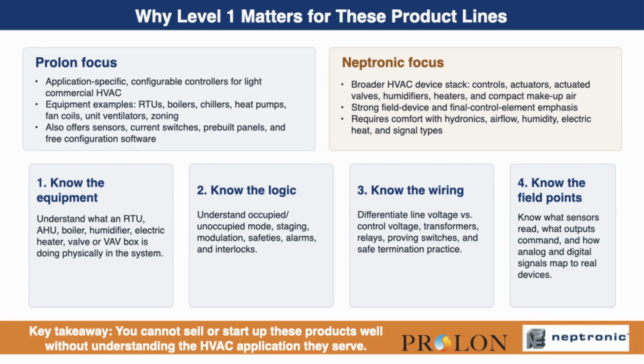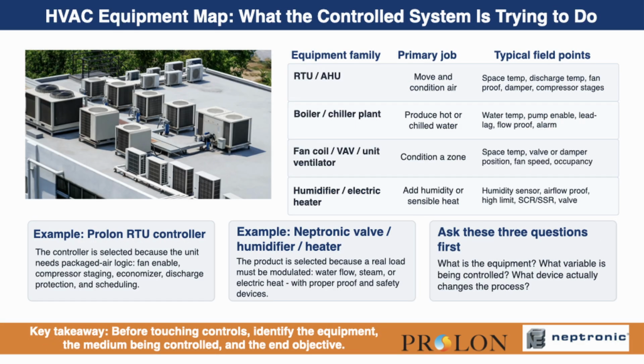The controller may look at space temperature, discharge temperature, fan proof, and perhaps an outdoor air damper position, and it will command outputs such as fan enable, compressor stage 1, compressor stage 2, and economizer or damper output, if present. That simple example shows why application knowledge must come before product knowledge. Before anyone touches controls, they need to identify the equipment and the objective of that equipment.